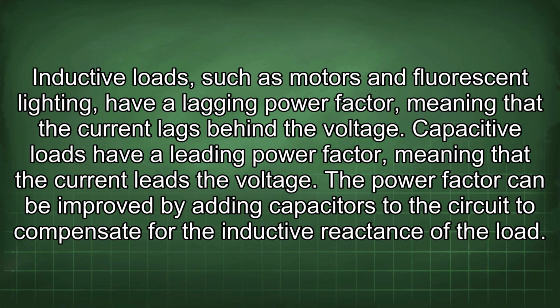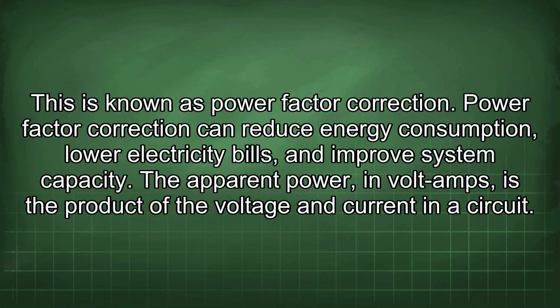The power factor can be improved by adding capacitors to the circuit to compensate for the inductive reactance of the load. This is known as power factor correction. Power factor correction can reduce energy consumption, lower electricity bills, and improve system capacity.